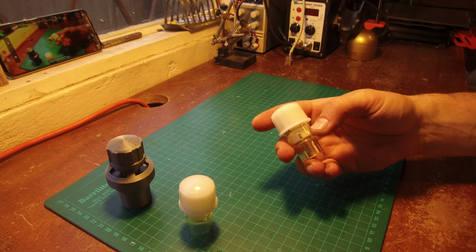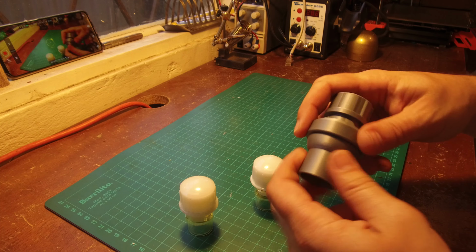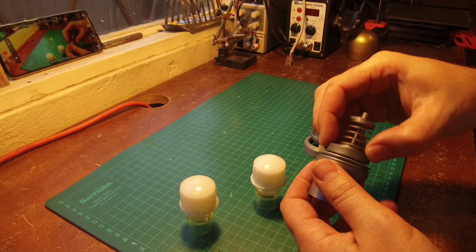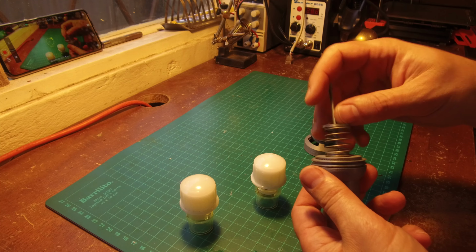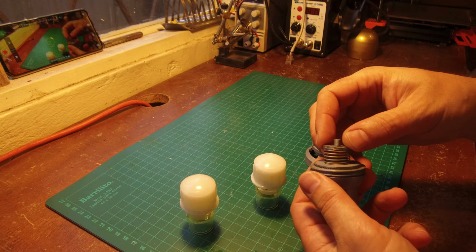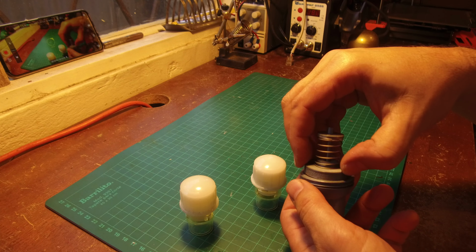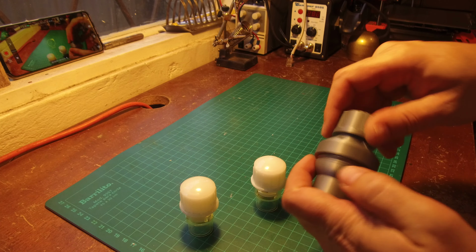Now these PEEP valves, positive end expiratory pressure, basically hold pressure inside the circuit. This works the following way. This thing blocks the airway and is held in place by this spring. When you screw this down, the spring pushes harder against it, so it holds more pressure in the airway. When there's too much pressure, this will go up and there will be pressure relief, right?